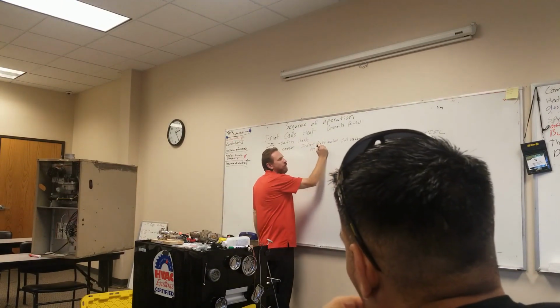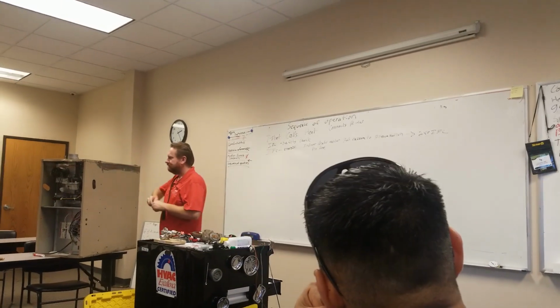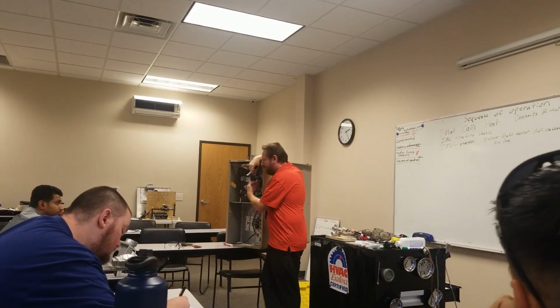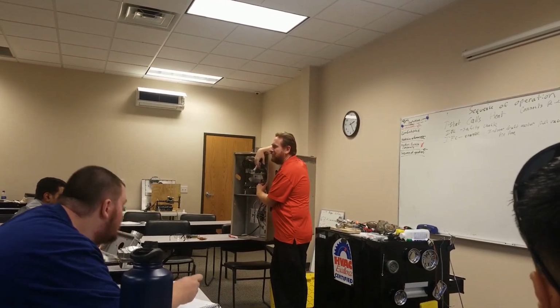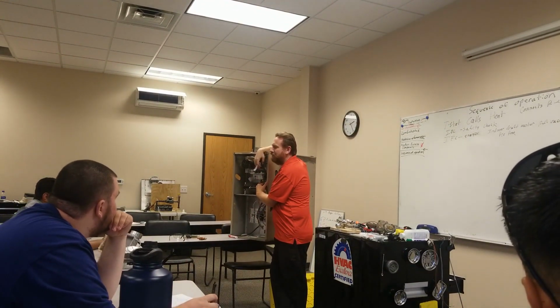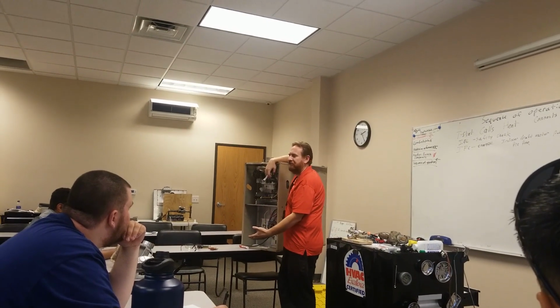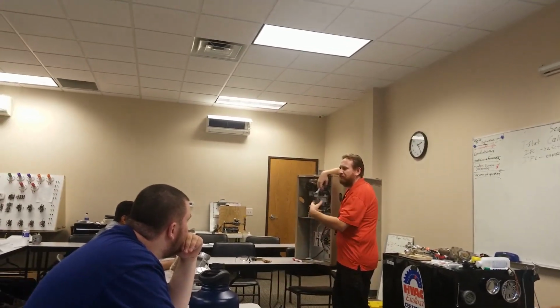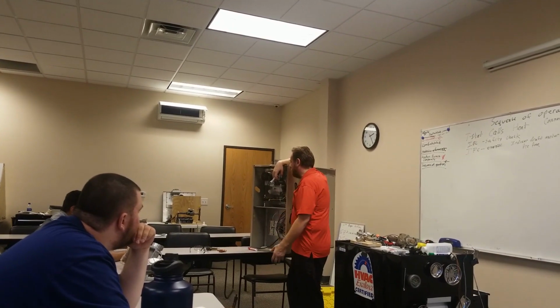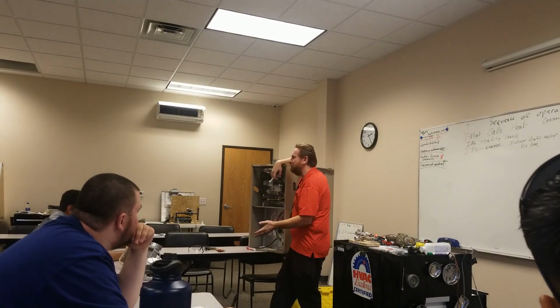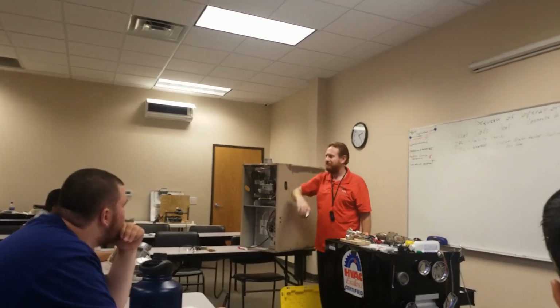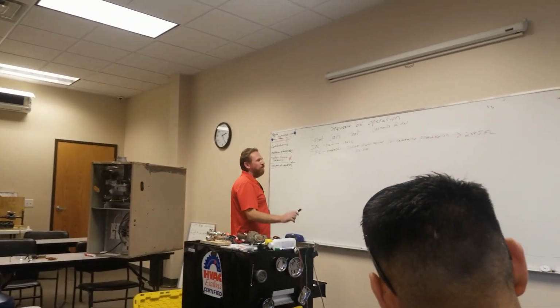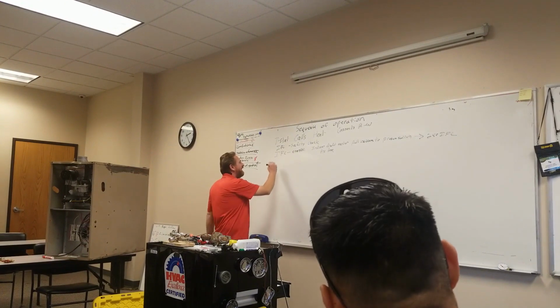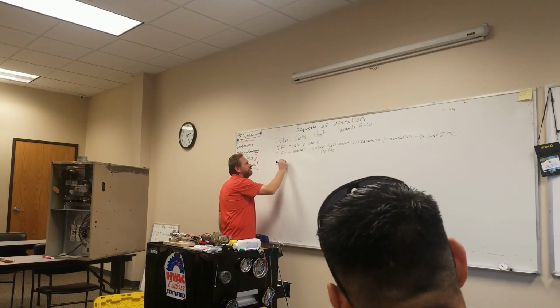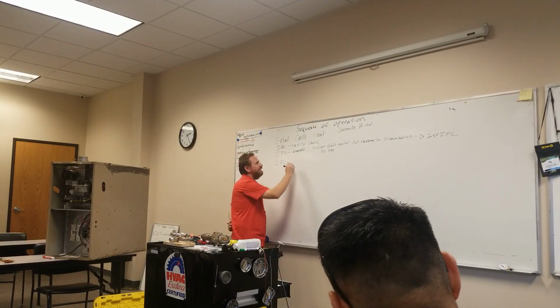A pre-purge means maybe it was just running and there's still some natural gas left in there. Maybe there were some cleaning supplies the customer had in the closet. Maybe there's a car in the garage and there were some fumes. It's going to run a 30-second pre-purge to get any of the fumes out of that heat exchanger. Nice of it, right? Just to make sure. Once it does that, the IFC, the Integrated Furnace Controller, is going to then energize what?